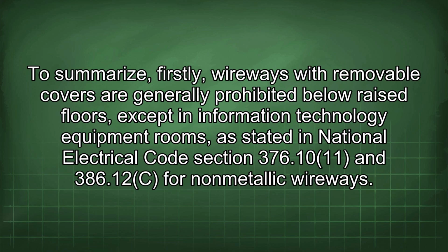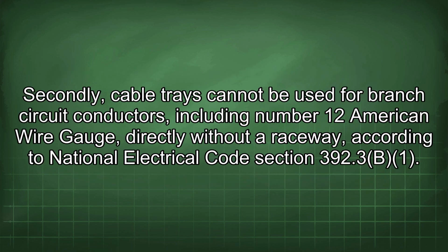To summarize, firstly, wireways with removable covers are generally prohibited below raised floors except in information technology equipment rooms, as stated in National Electrical Code Section 376.10(11) and 386.12(C) for non-metallic wireways.